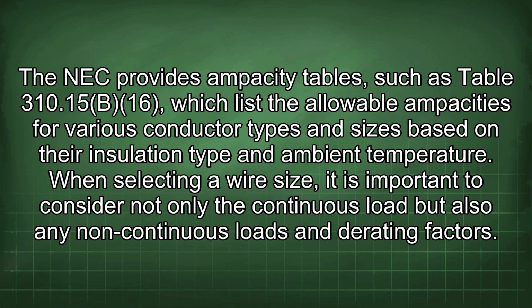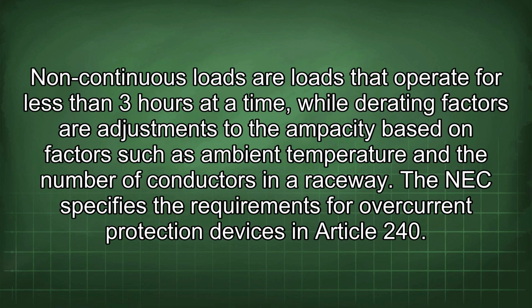When selecting a wire size, it is important to consider not only the continuous load but also any non-continuous loads and derating factors. Non-continuous loads are loads that operate for less than 3 hours at a time, while derating factors are adjustments to the ampacity based on factors such as ambient temperature and the number of conductors in a raceway. The NEC specifies the requirements for overcurrent protection devices in Article 240.